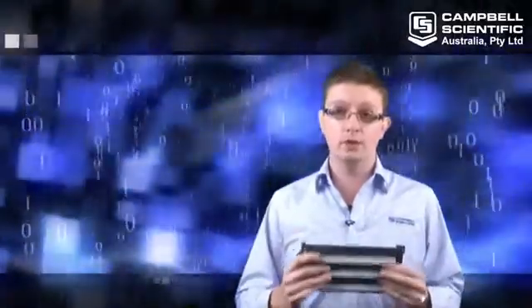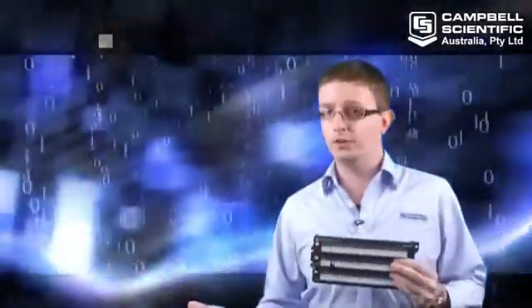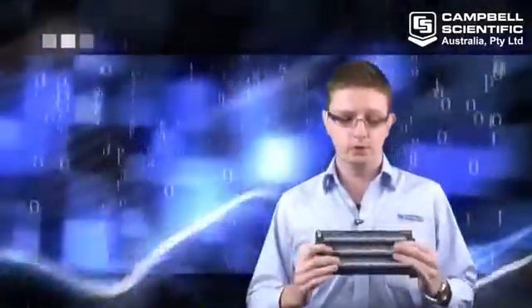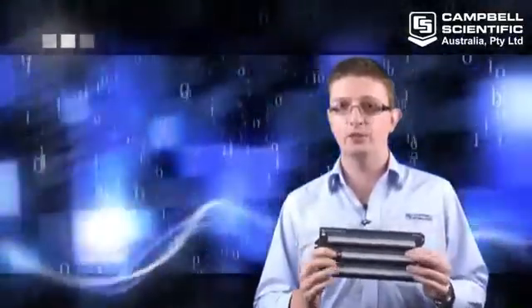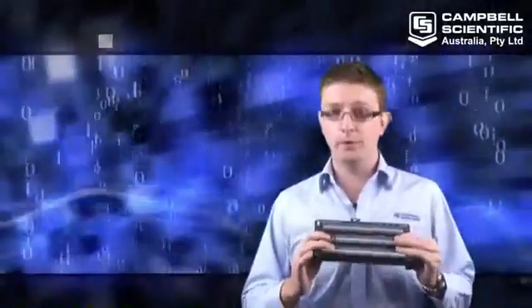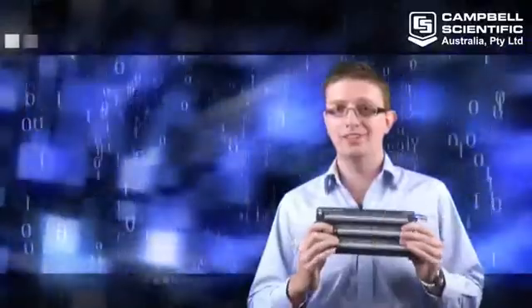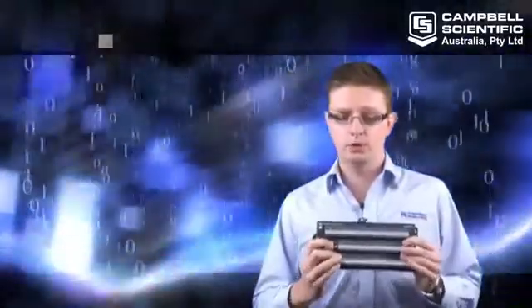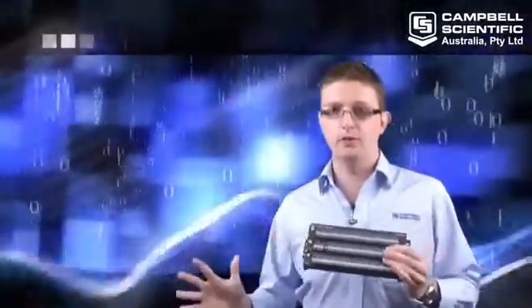So if eight channels isn't enough on your CR1000, you don't necessarily need to buy a new logger. You can get one of these multiplexers to increase the amount of analog sensors that you can measure on your CR1000. So this video is going to be about wiring it up. To wire this to a CR1000, you will need six wires for the connection between this and your datalogger.